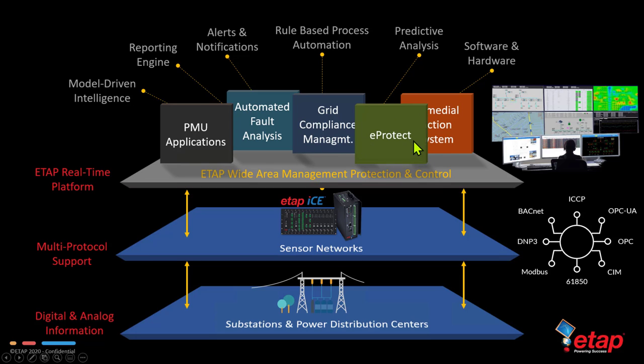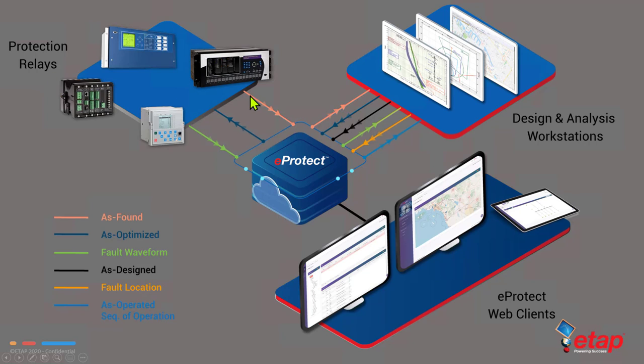Of course, in this webinar, we'll focus primarily on eProtect. eProtect communicates with the protection relays by essentially retrieving the as-found settings, which are then passed on to the design and analysis workstation. The engineer performs the electrical system study and the optimization and passes the as-optimized results back to eProtect, and it is essentially hosted and maintained inside the central database.